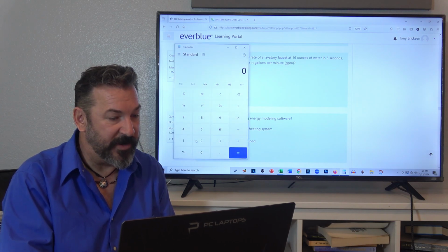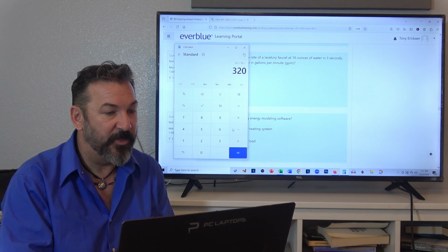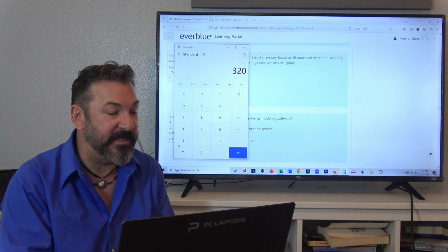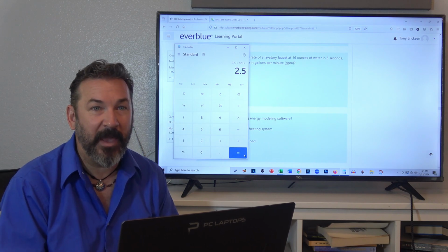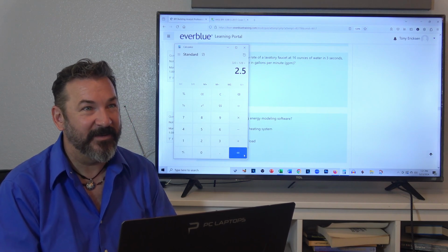20 times 16 equals 320, divided by how many ounces in a gallon? 128. There you go. 2.5 gallons per minute.